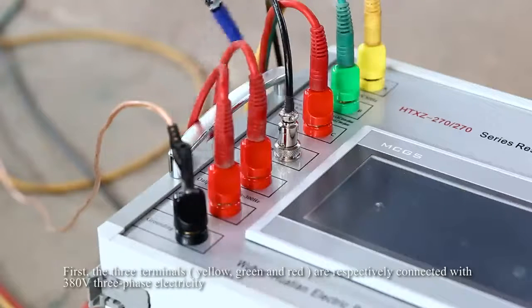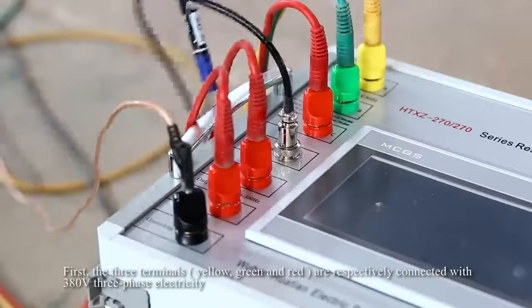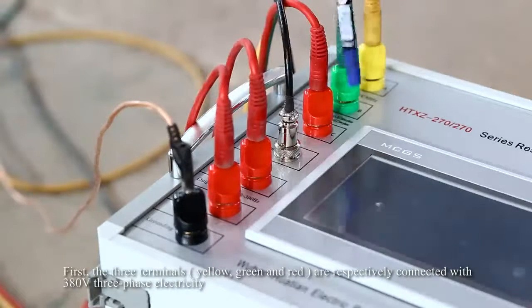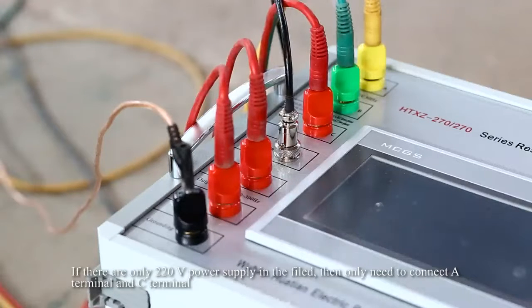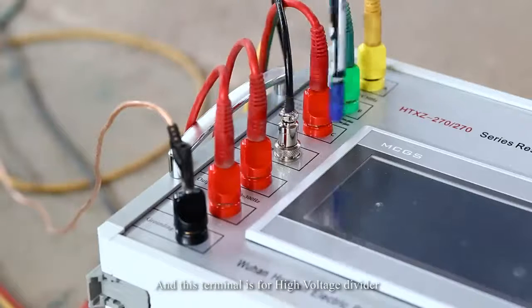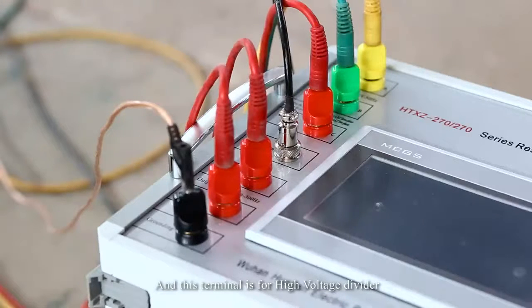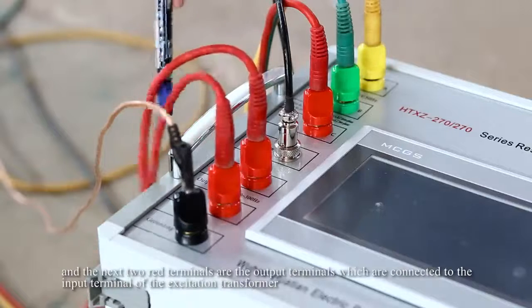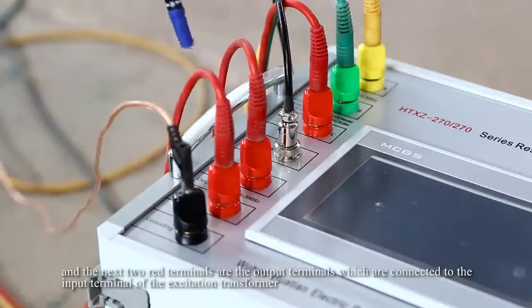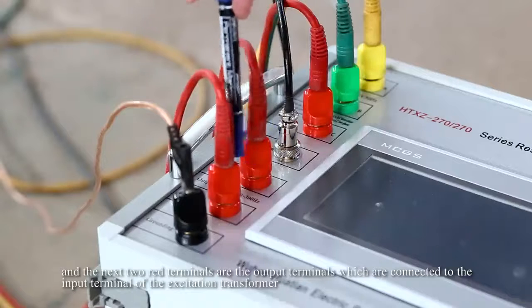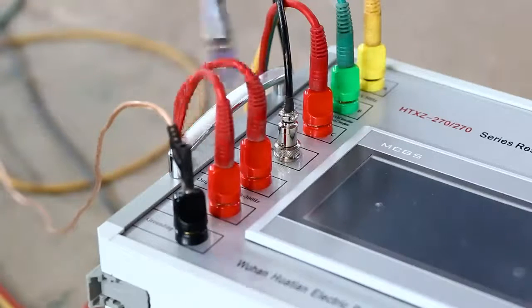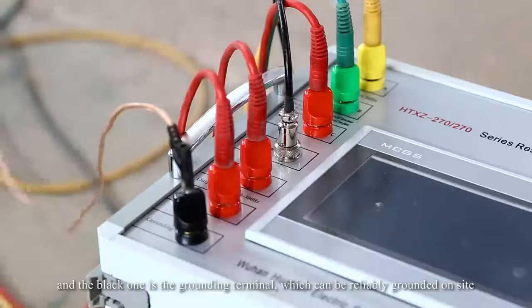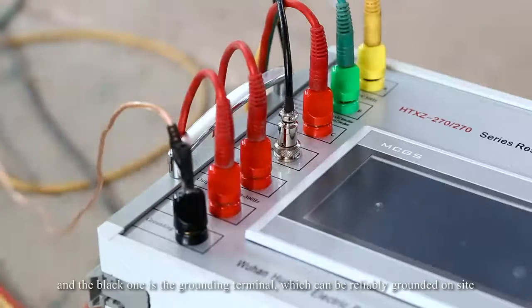First, the three terminals, yellow, green, and red, are respectively connected with 380 volts three-phase electricity. If there is only 220 volt power supply in the field, then you only need to connect the A terminal and C terminal, and the power of the instrument will be halved. This terminal is for the high voltage divider. The next two red terminals are the output terminals, which are connected to the input terminal of the excitation transformer. And the black one is the grounding terminal, which can be reliably grounded on site.